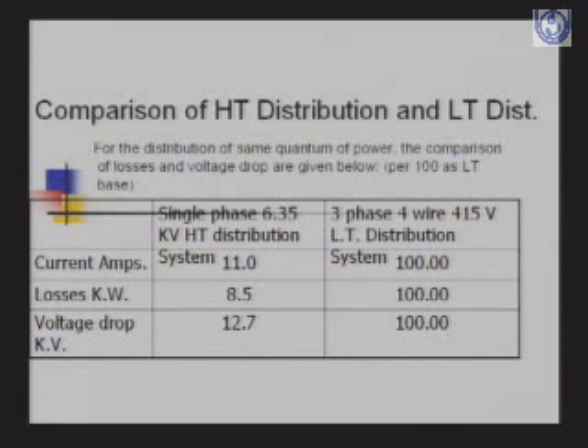If you compare the HT distribution and the LT distribution for the distribution of the same quantum of power, the comparison of losses and voltage drop is as below. For LT we have taken 100 as the base. If the current in the LT system is 100, then in the single phase HT high voltage distribution system, the current will become 11 ampere. If the losses in the 3-phase, 4-wire LT distribution system are 100, they will become only 8.5 in the high voltage distribution system, and the voltage drop, if it is 100, will become 12.7.